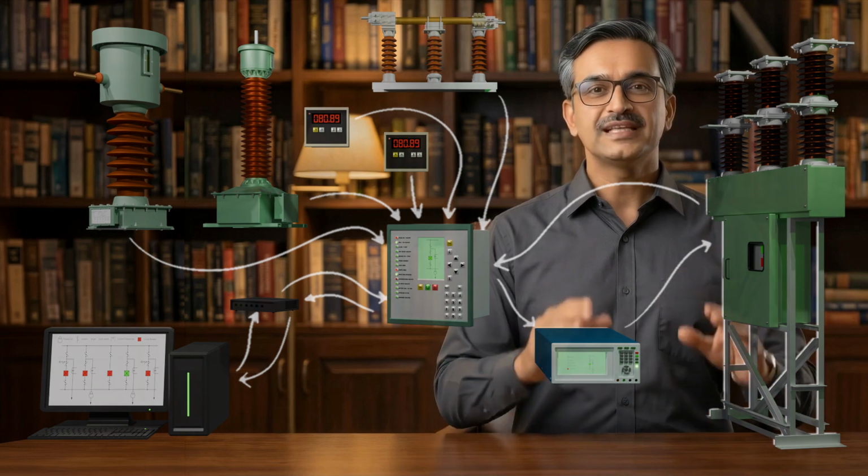Now, although all the equipment associated with a bay already have their physical, mechanical, and electrical interlockings, still the BCU can provide programmed operation with interlocking logic. So, whenever a command is received either from SCADA or directly from the BCU itself through its input module, the central processing unit verifies all the interlocking logic conditions. If everything is okay, then only it sends the instruction signal to the IED, that is, the intelligent electronic device of the associated circuit breaker or isolator for operation.